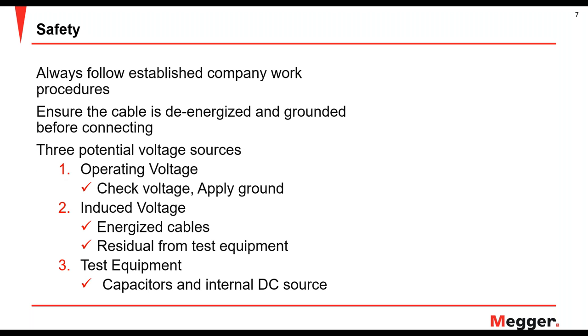First things first, with Megger, we always say follow your established company's work procedures — meaning if you have to wear gloves or use a hot stick to make any connections, do so. Also ensure that the cable is de-energized and grounded before connecting any equipment. This eliminates the potential for any operating voltage; if you're on the wrong cable, you'd know because the other end is already grounded. You also have to be aware of induced voltages by any cables running parallel, and also be mindful that the test equipment itself has capacitors and internal DC storage, which is also a potential for high voltage.